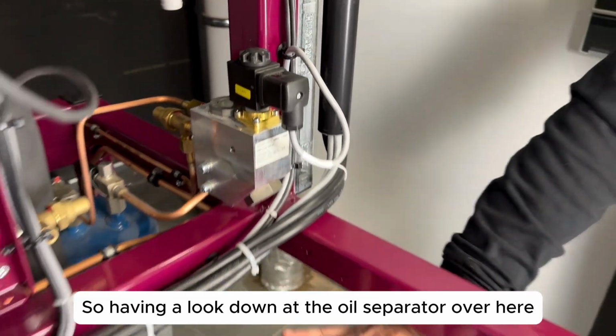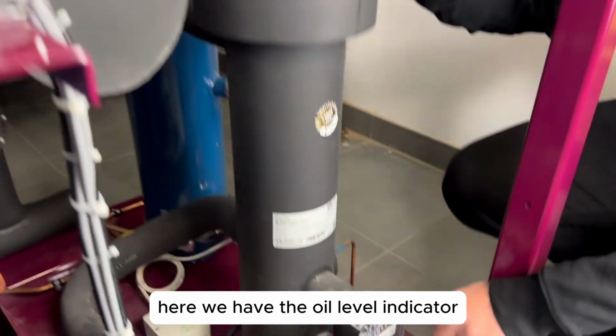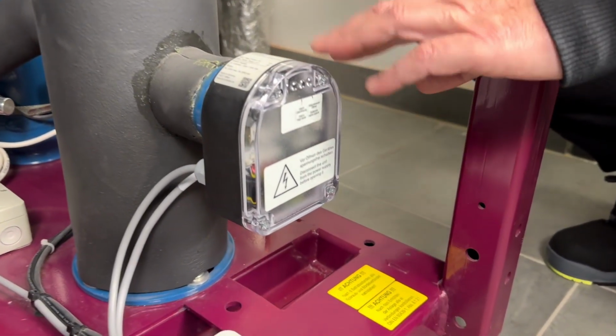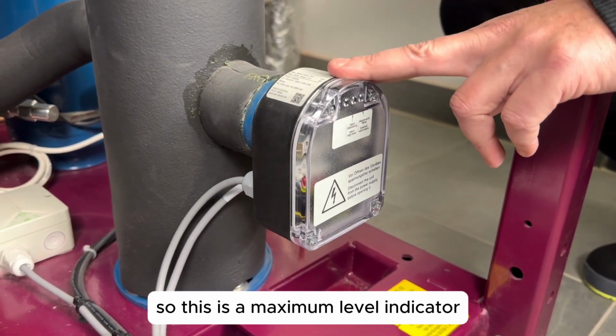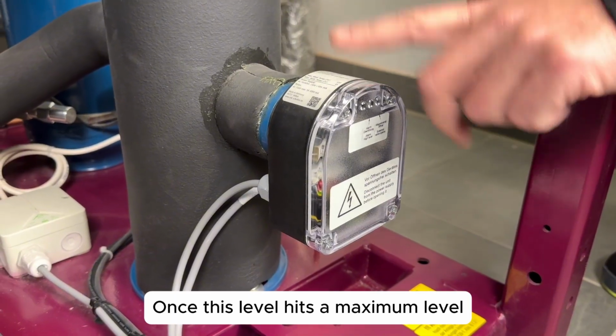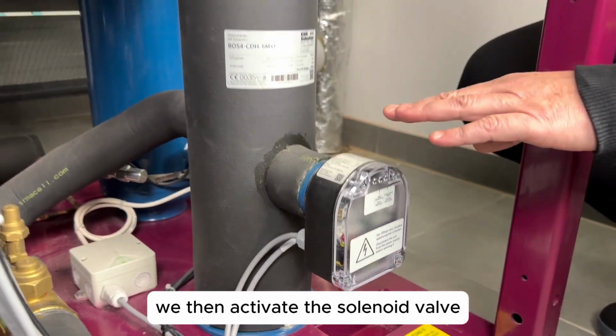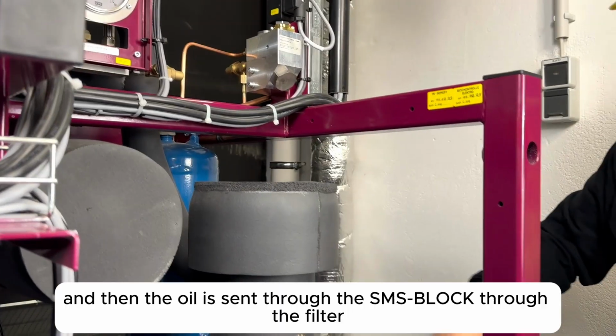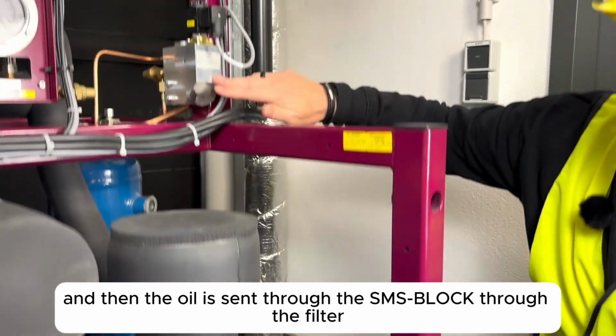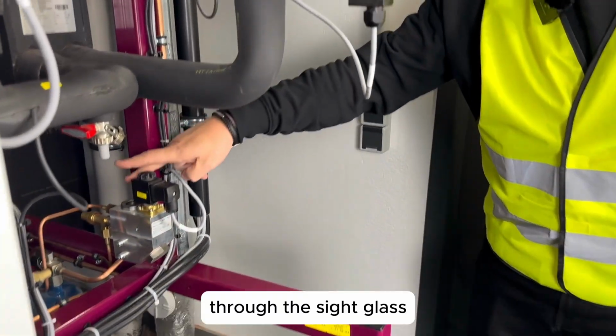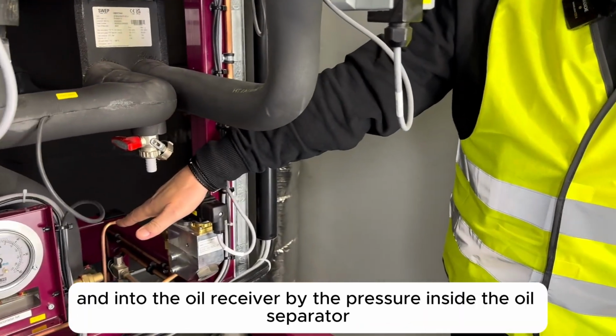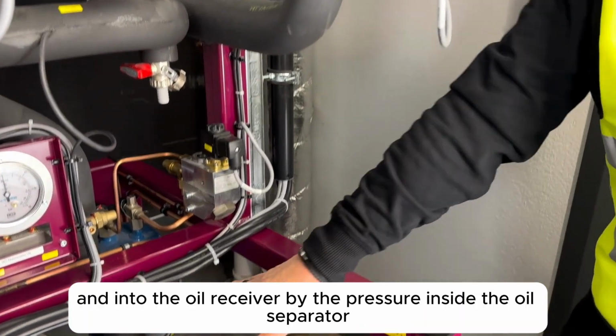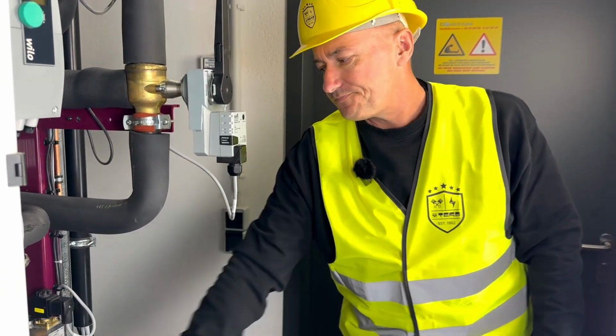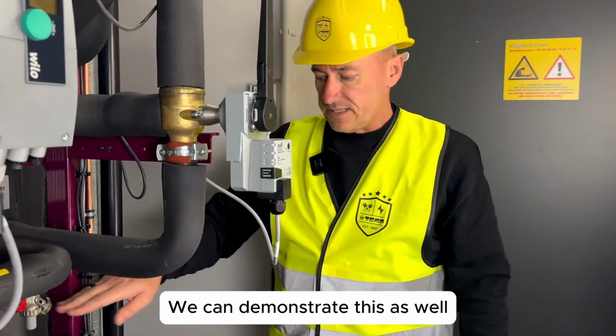So having a look down at the oil separator over here, we have the oil level indicator. So this is a maximum level indicator. Once this level hits a maximum level, we then activate the solenoid valve, and then the oil is sent through the SMS block, through the filter, through the sight glass, and into the oil receiver via the pressure inside the oil separator. We can demonstrate this as well.